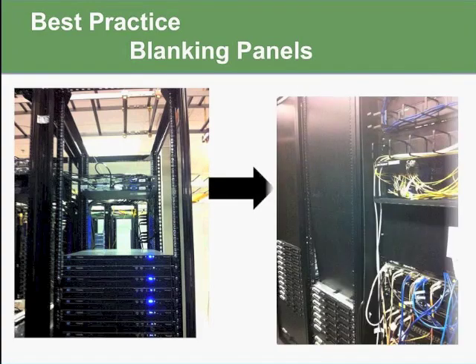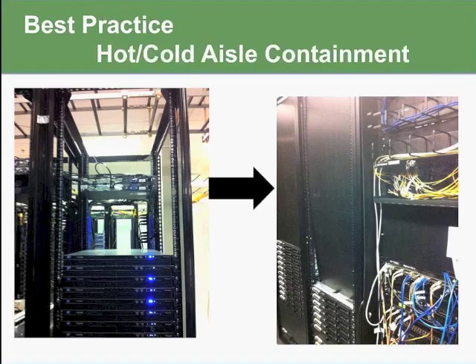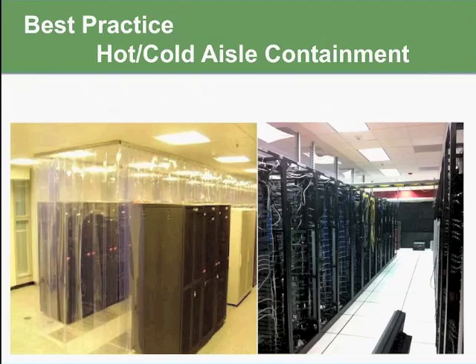The answer really is to simply plug those gaps with blanking panels, and you may have to put tape around where you have cabling and that sort of thing, but generally it's a very simple, low-tech, low-cost solution to improving the operational efficiency of the cooling in your data center. And a second best practice, again, relatively low cost and low tech, is hot aisle or cold aisle containment.